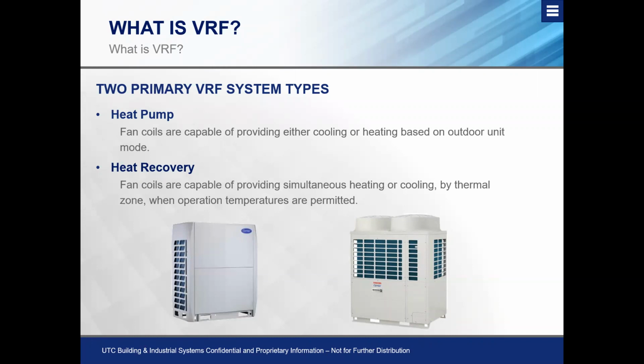So there are two primary VRF system types: heat pump, which is all heat, all cool, just like any traditional heat pump or split system. And then we have what the technology is typically associated with, which is the heat recovery style of systems, which is that simultaneous heating or cooling. And a great way to tell them apart is if your system has an FS or a flow selector box or a branch box, then you know that that system is a heat recovery system. If your system only has two pipes, then you're pretty sure it's a heat pump system.